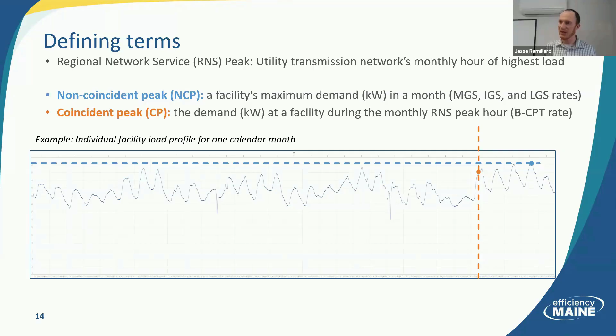In the graph here, the blue line represents the non-coincident peak, at the point of highest load for this load profile. But you see there are lots of peaks, and if you miss one, there are others just below it. So to make a meaningful difference on your demand bill on a standard bill, you've got to trim multiple peaks usually. Whereas with this coincident peak rate structure, you just are going after a single hour, and if you can hit that hour, you probably get some good cost savings on your demand charges.